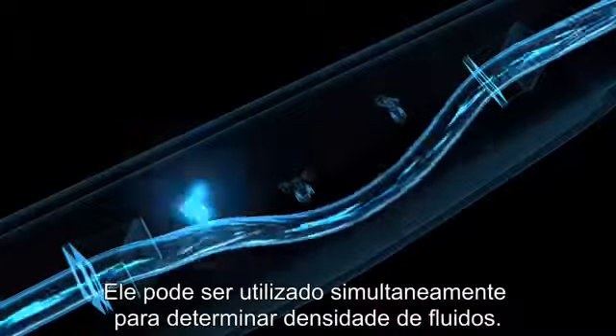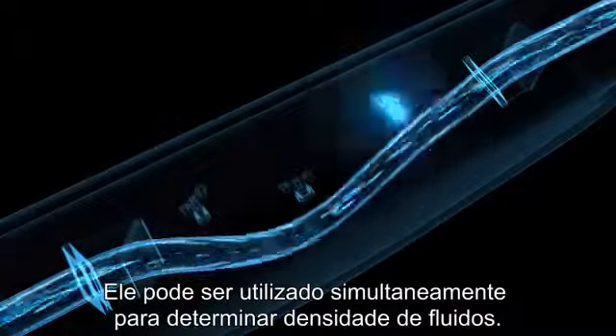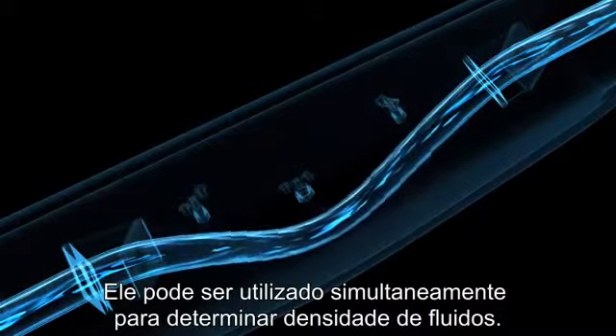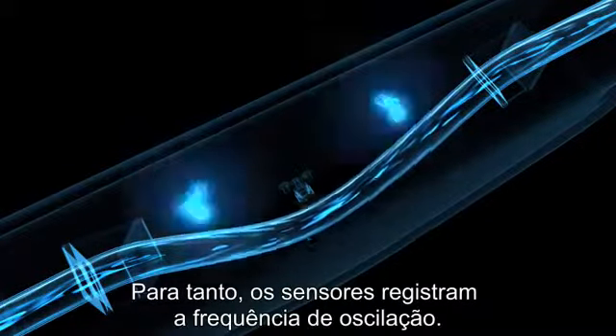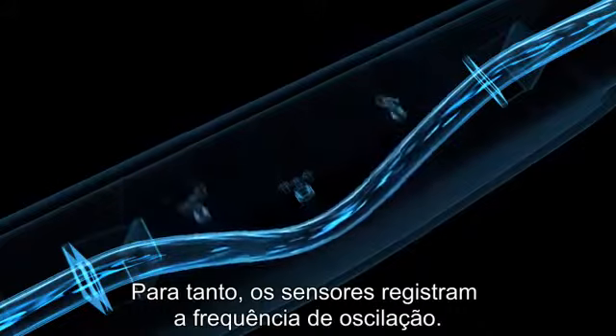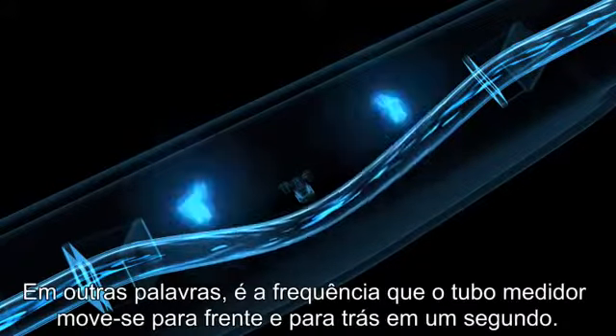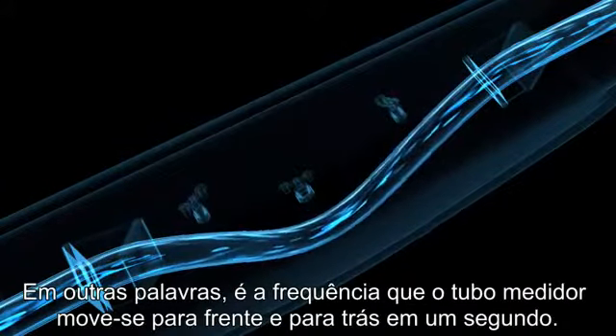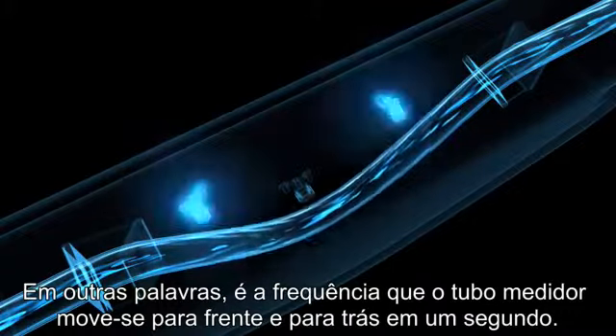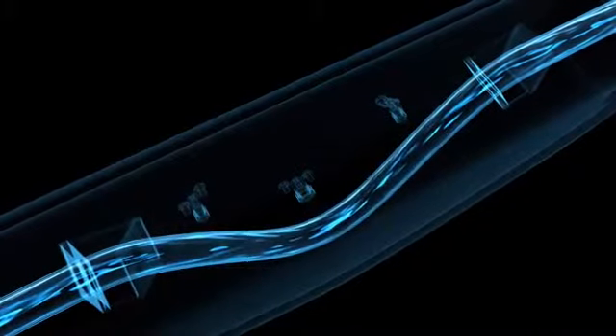It can also be used to simultaneously determine the density of the flowing fluid. To do so, the sensors also register the oscillating frequency. In other words, how often the measuring tube moves back and forth in 1 second.